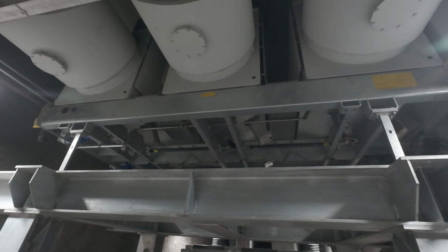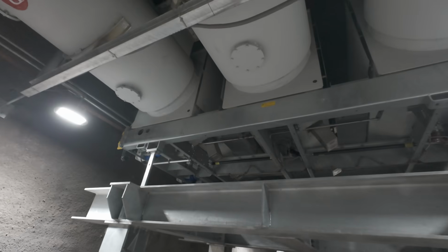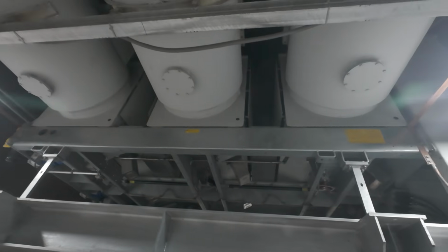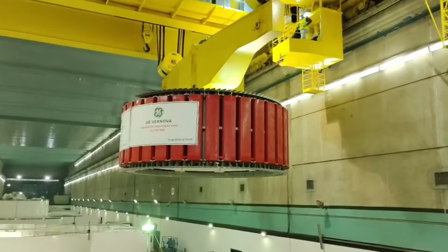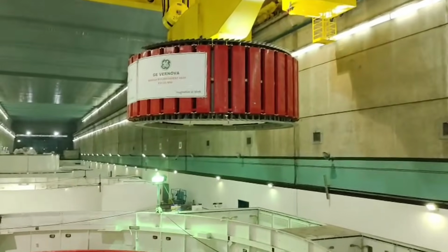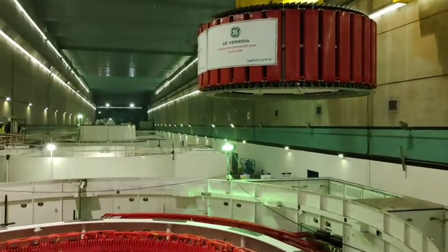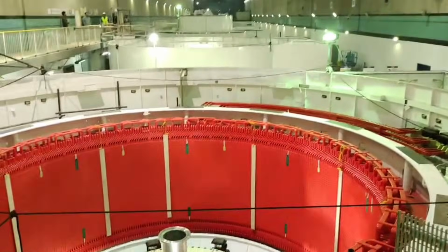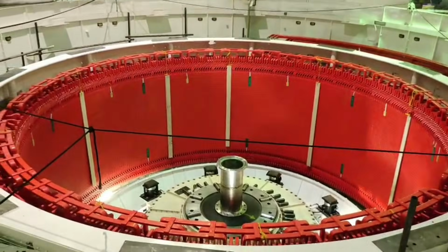Because if voltage becomes too high while frequency is still low, the magnetic core can saturate, causing destructive overheating inside both the generator and the transformer. And finally, there is the power system stabilizer, or PSS. This system detects tiny oscillations across the transmission network, then injects a corrective signal into the AVR to stabilize the entire grid. In some situations, this system can literally help prevent regional blackouts.